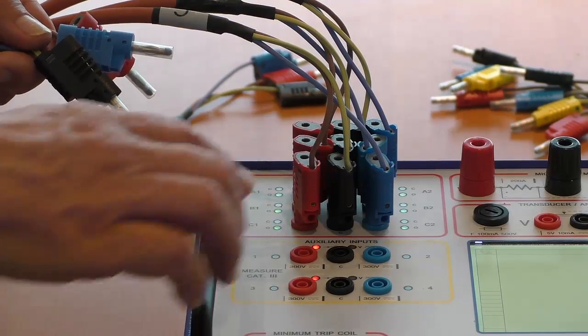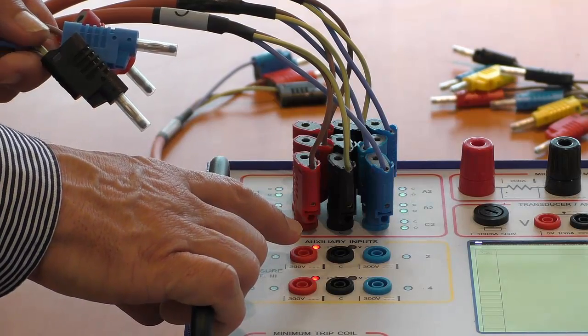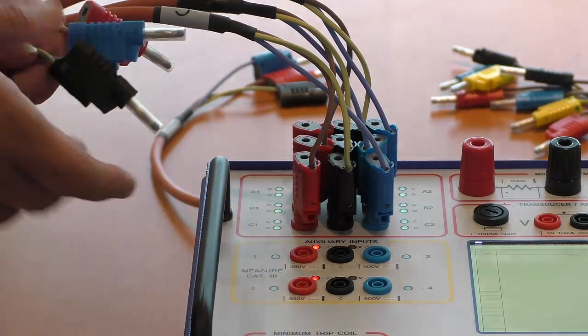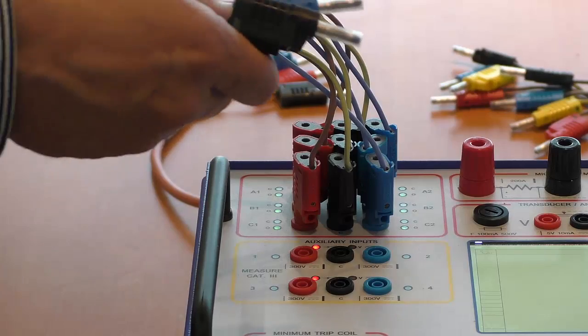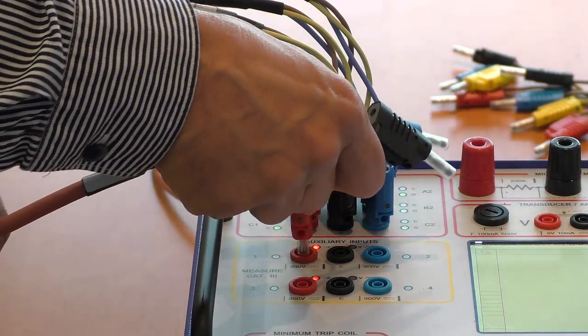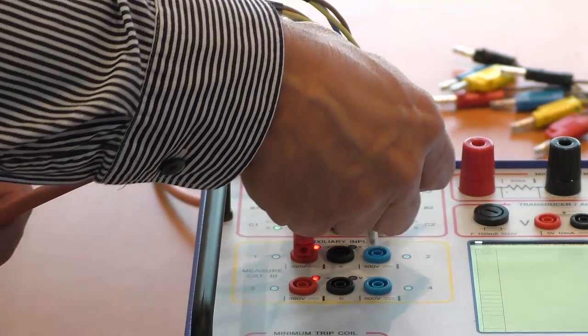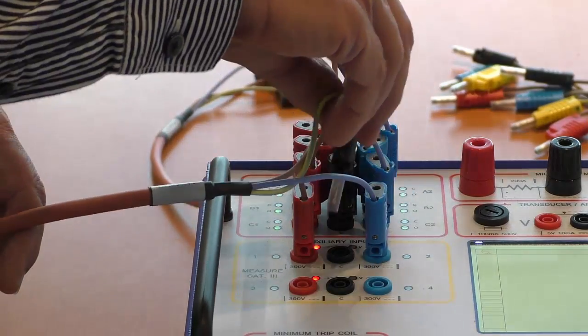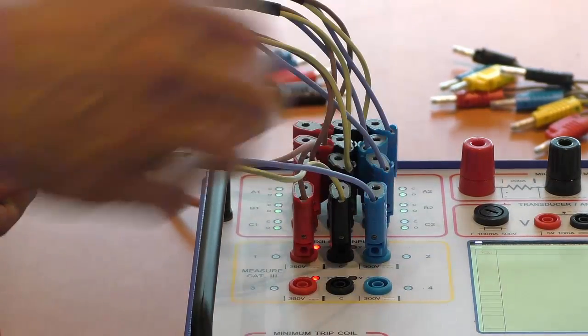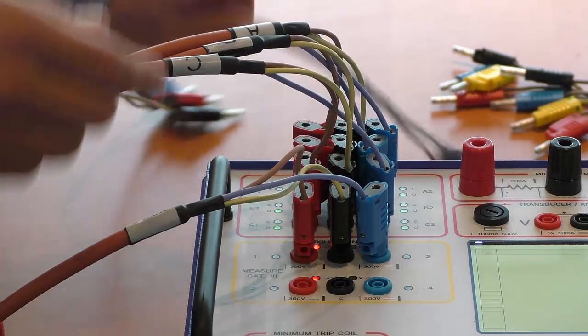A number of inputs are provided for auxiliary inputs to monitor auxiliary contacts. These are inserted in a similar fashion according to the color coding as the main contacts, and you can monitor up to 4 contacts in this way.